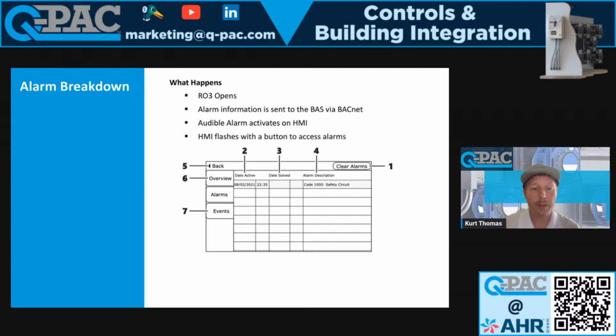And whenever you hit that button, this screen is going to show up, and it's just going to list all of the active alarms. So the alarm on this example alarm description is saying, hey, code 1000, and that is a safety circuit alarm. So that's just saying, hey, one of your safety sensors has tripped, and we are in safe mode. We are not running the fans. The fans don't even have power. So fix that safety circuit before we can run.